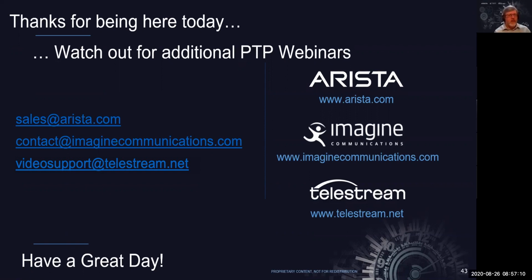Definitely as part of your debugging, what you can also look at is things like, for instance, if one device's timeout was set wrong, that device may think it's failed when it hasn't. Make sure the timeout values are set the same on both links, and the message rates are set properly. If one was set to 2 messages per second, or 1 message per second, and the other device was configured expecting 1 message every 2 seconds, or 2 messages a second, that would cause issues.